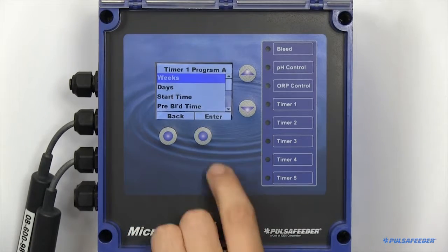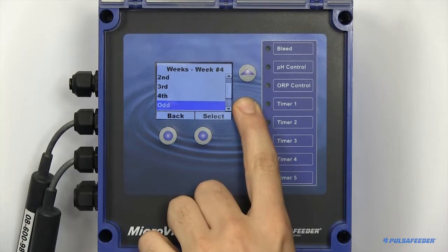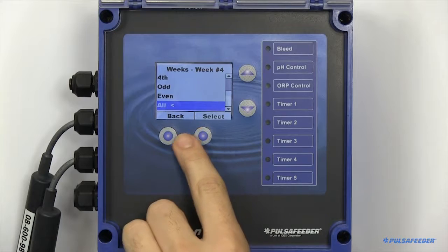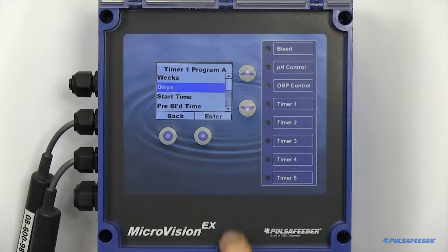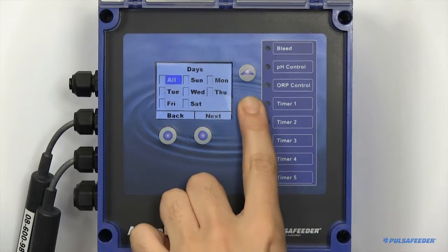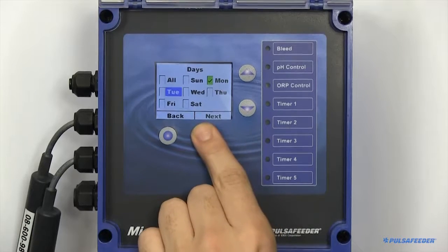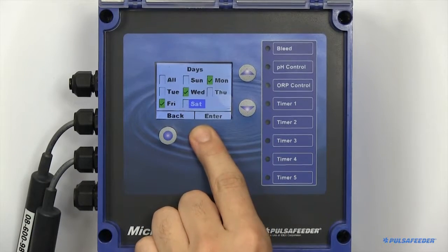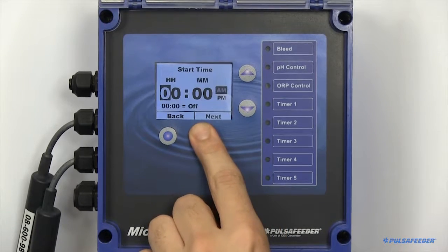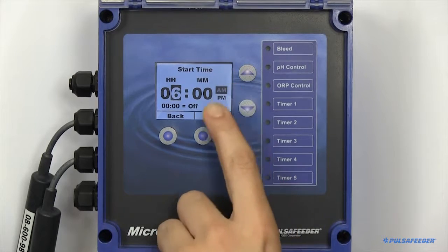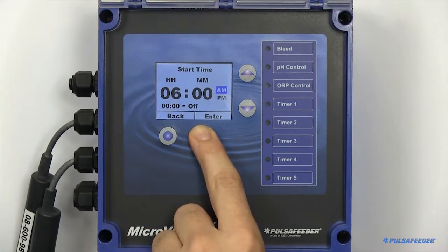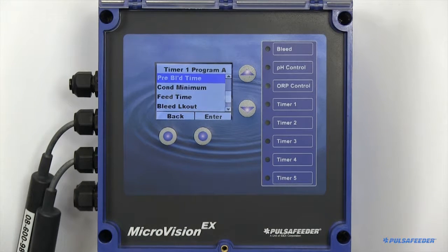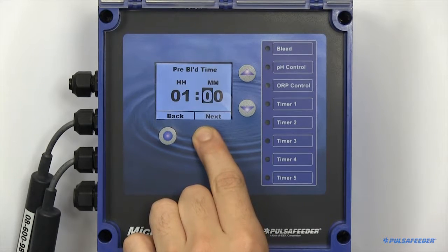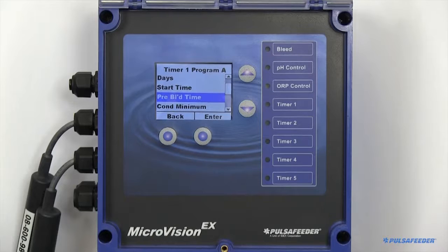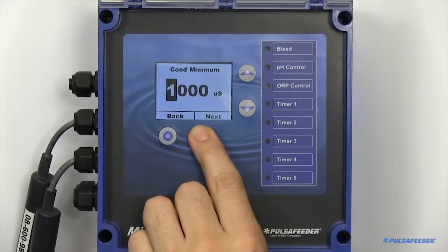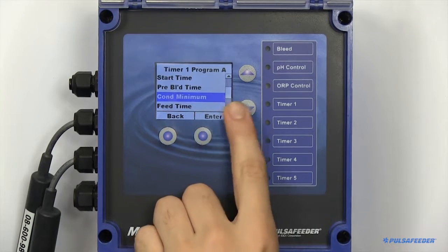A 28-day timer can be set to run on any individual week, odd weeks, even weeks, or every week. Any combination of weekday can also be selected. You may choose all of the days or a single day. The start time is when you would like to either begin your feed cycle or a pre-bleed if applicable. A pre-bleed time is the maximum amount of time you would like the bleed function to be force-enabled prior to a feed cycle. If there's a minimum conductivity you would like the tower to reach to immediately begin your feed cycle, this can also be set.